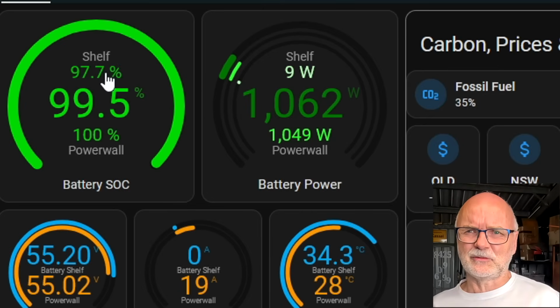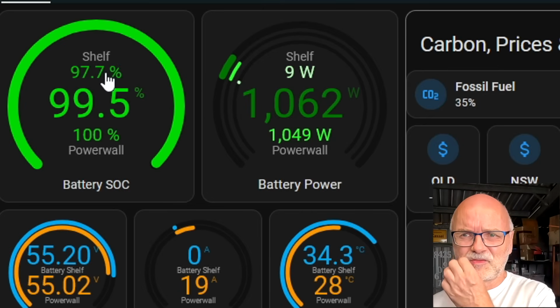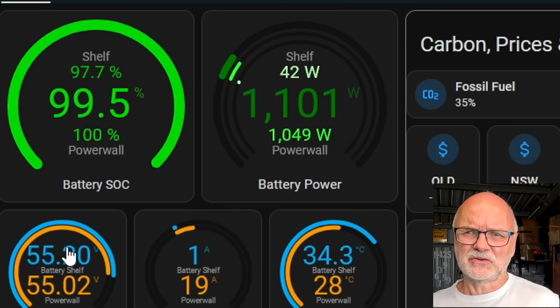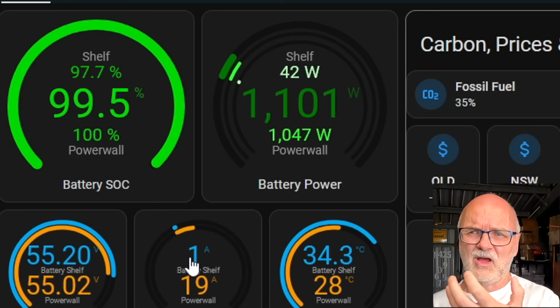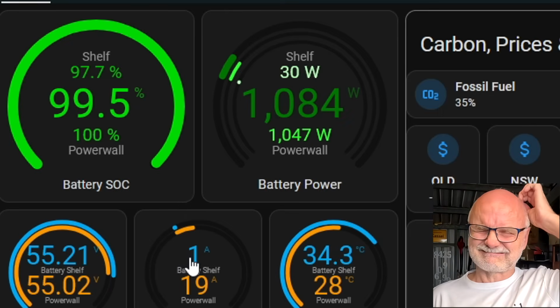The smart shunt has still not reset to 100% here for the battery shelf, because it should reset once we are over 55.1 volts for 3 minutes and the current is under 2% of 1C, which is around 16 amps, so it must be under 16 amps then. So yeah, let's see, whatever.